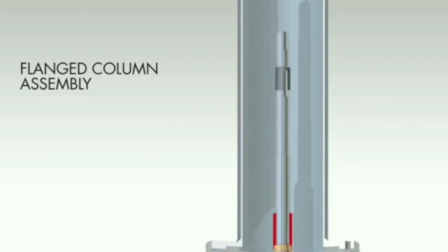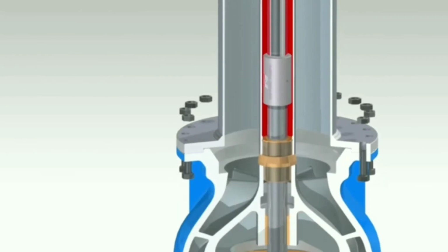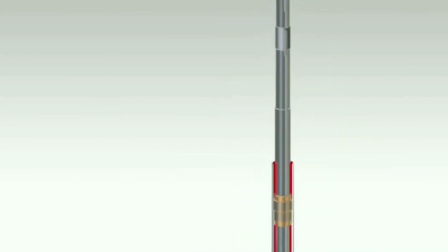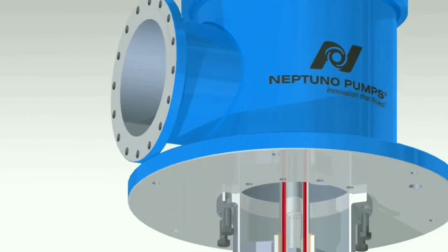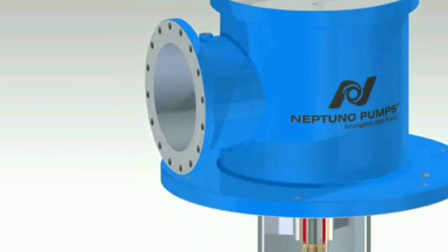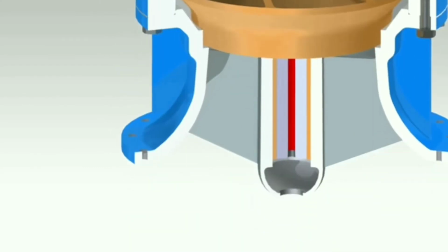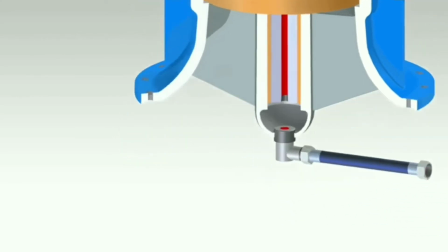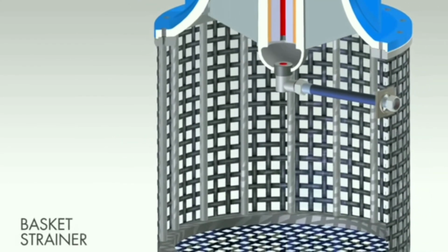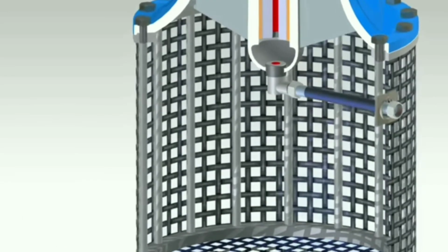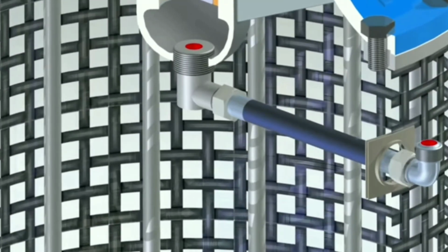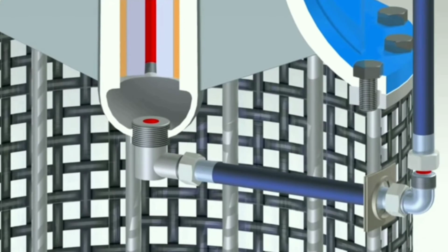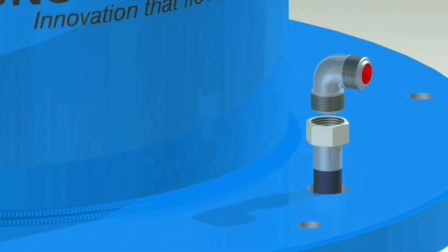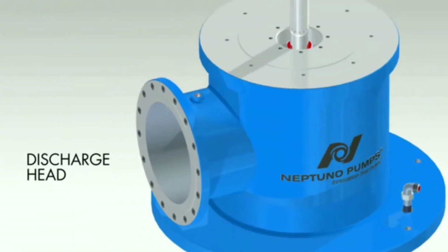Later, when the water leaves the last diffuser bowl, it passes through a long vertical column pipe as it rises up the well bore toward the surface. The spinning shaft inside the column is supported at 3 or 5 foot intervals with sleeve bushings that are mounted inside the column and lubricated by the water moving past them. At the surface is the pump discharge head, which allows the flow to change direction towards the discharge pipe.